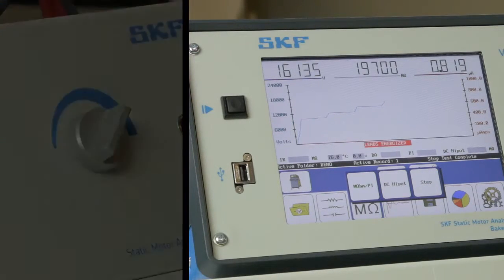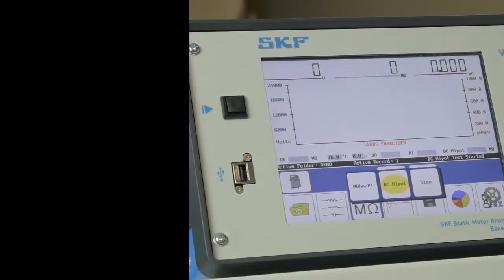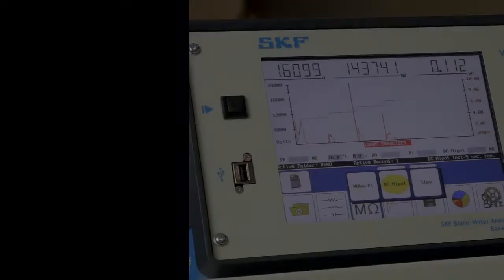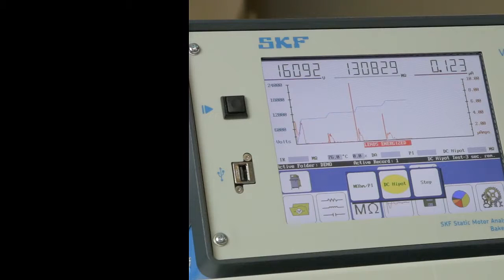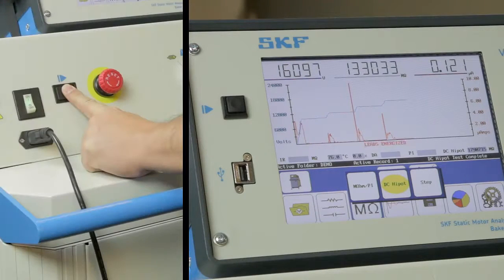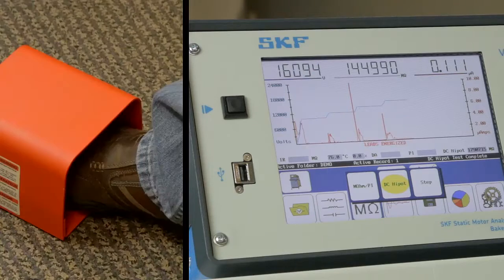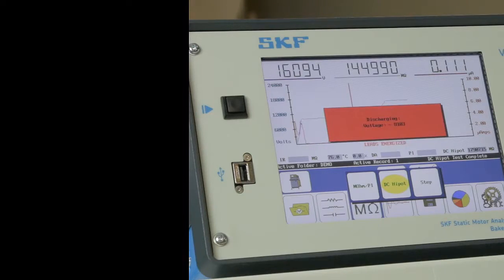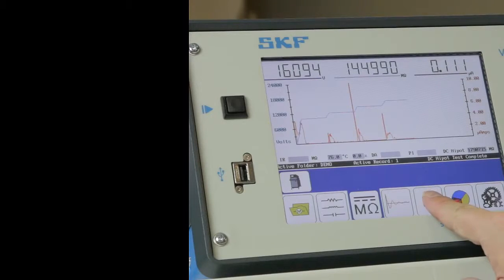However, when you reach your final test voltage, press DC HiPot instead of step. Again, this test will last for 1 minute by default. When the HiPot test is complete, release the push to test button or the foot switch. Save the data.